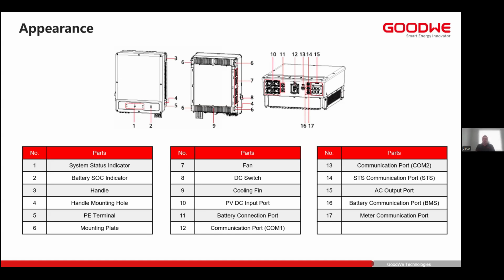For easy installation, there is a handle which can be used on both sides, for mounting and for easy lifting. The rest includes the fan, the DC switch, cooling fins, and then at the bottom, we've got all the input ports. All MPPT and string inputs will be on the left side, and then we have the battery input. Next to that is the communications port. That's where all the communications for parallel or third-party integration will be done through those ports. Then we have the battery communication port as well as the meter comms ports. And then what is important here is number 15, the AC output port.